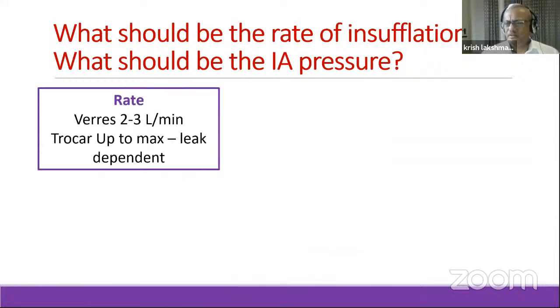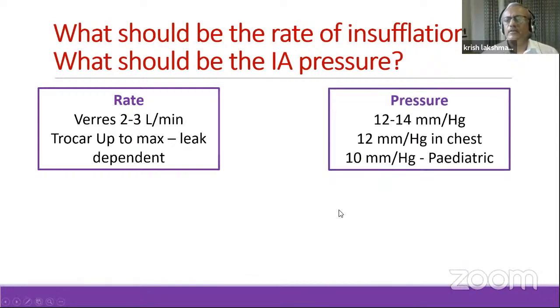The Veress needle has a very small caliber, so even if you set it at 20 liters per minute, it won't take it. The maximum you can have is 2 to 3 liters per minute. With a trocar, it's up to the maximum that the insufflator can give. As I said, generally it is 20 and it can be as high as 40. And it is leak dependent.